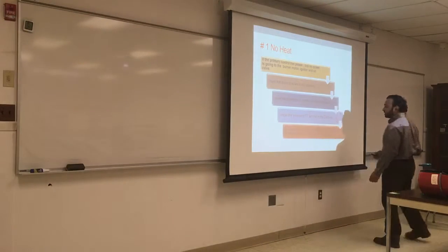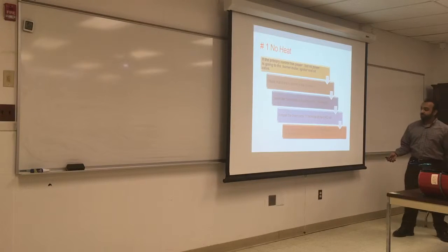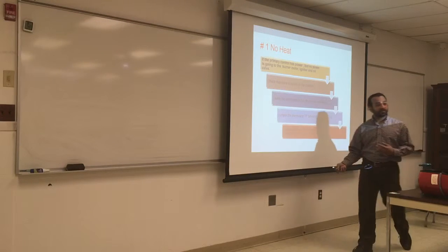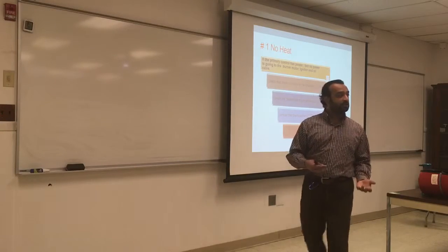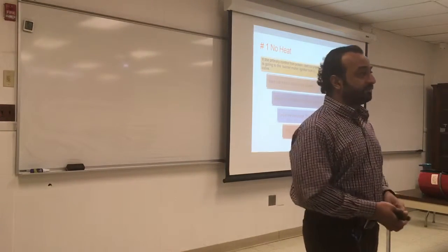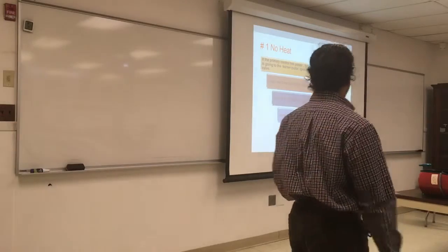If the burner does not start, jump on the F F terminals. If the burner starts, then the cad cell is bad. So it's going to be either the cad cell or the thermostat. If none of that works, the primary is faulty, something is wrong with it. Change the primary.